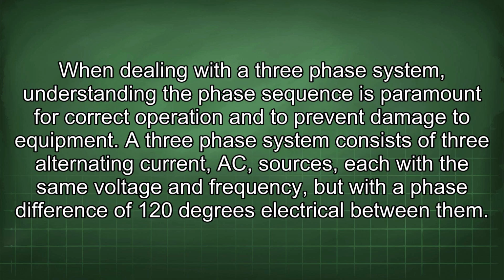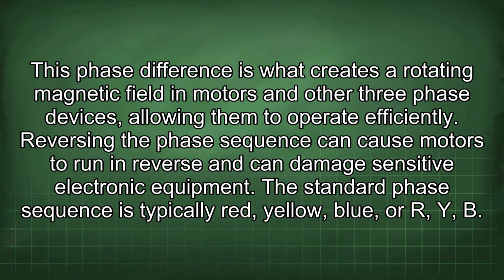When dealing with a three-phase system, understanding the phase sequence is paramount for correct operation and to prevent damage to equipment. A three-phase system consists of three alternating current (AC) sources, each with the same voltage and frequency, but with a phase difference of 120 degrees electrical between them. This phase difference is what creates a rotating magnetic field in motors and other three-phase devices, allowing them to operate efficiently. Reversing the phase sequence can cause motors to run in reverse and can damage sensitive electronic equipment.